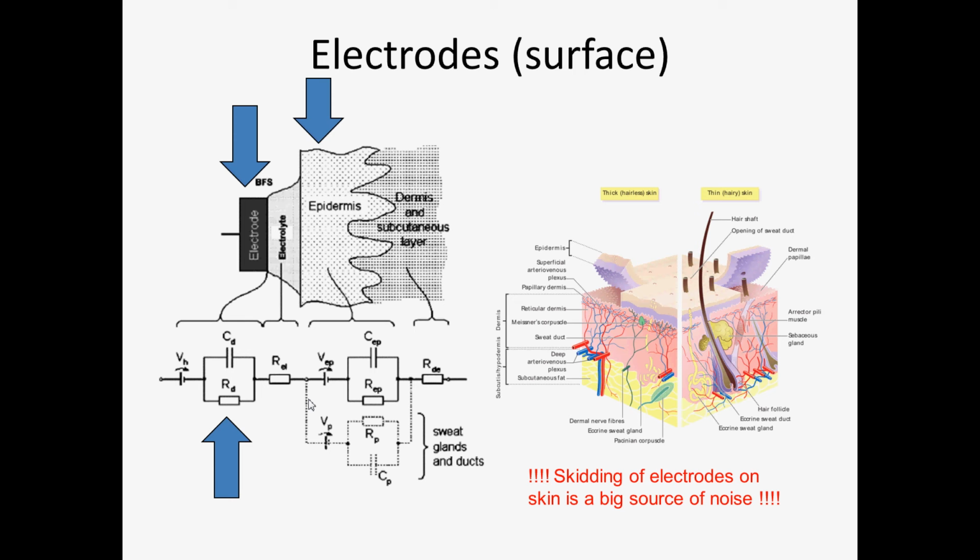Well, you fill the electrodes with electrolytic gel or glue. If there is a mat of hair squashed between the scalp and the electrode, the gel is going to smear. And when it smears, if you have nearby electrodes, guess what is going to happen? You're going to short electrodes out. And this is one of the major causes of boundary alteration in the brain activation maps done with EEG signals.